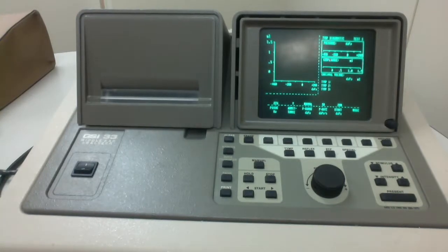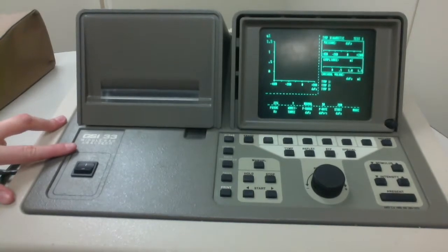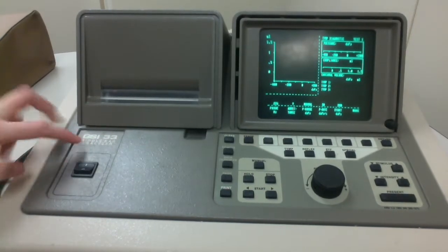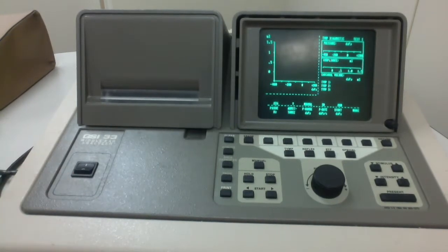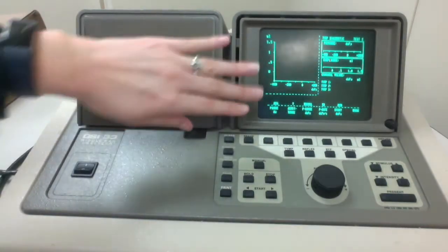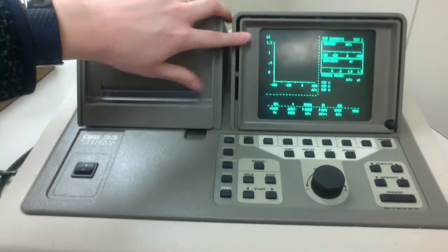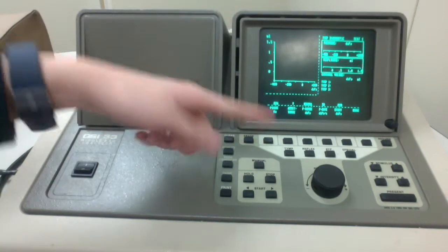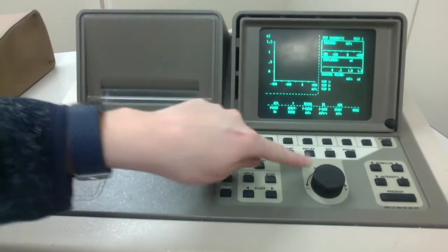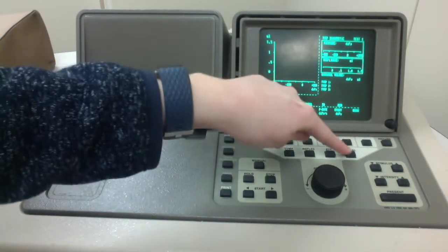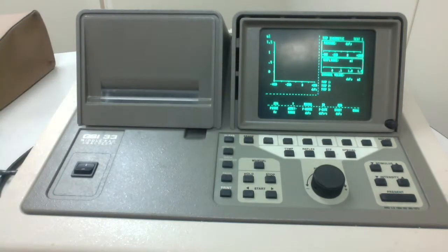So this video is going to be covering acoustic admittance testing, which will include tympanometry, acoustic reflexes, and then acoustic decay. So I want to start by getting you familiar with our equipment. This is our main middle ear analyzer that we have in the lab. It's our GSI 33. The power switch is here. Usually when you flip it on, it takes a few minutes to initialize, so I already had it set up for us. It automatically defaults to our tympanometry setting, and if we want to change the setting, which we will do later on, acoustic reflex would be there, and then this one labeled special, that's what we use for acoustic decay.